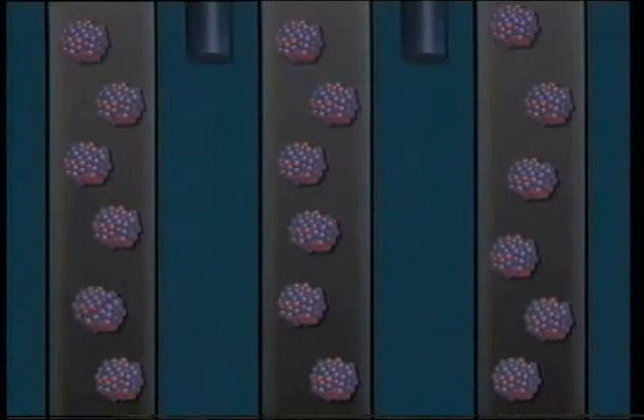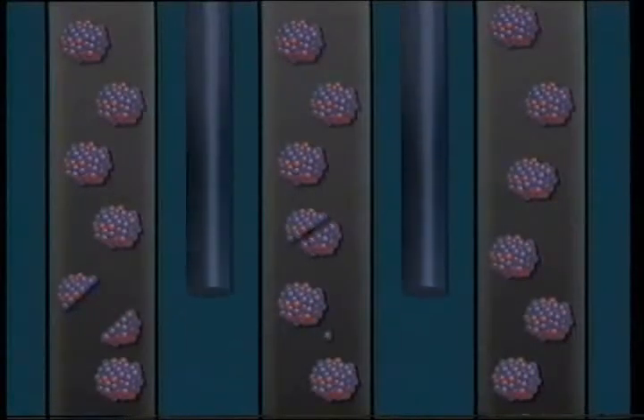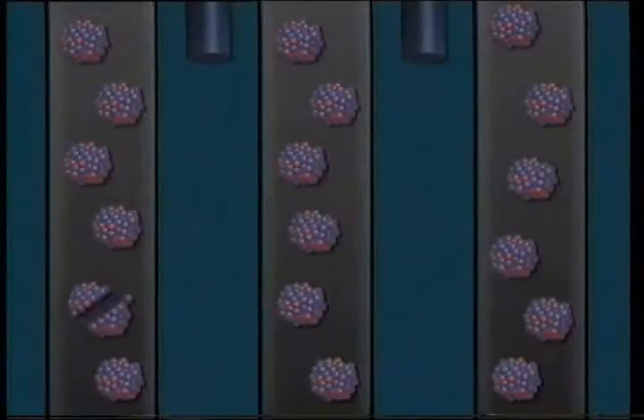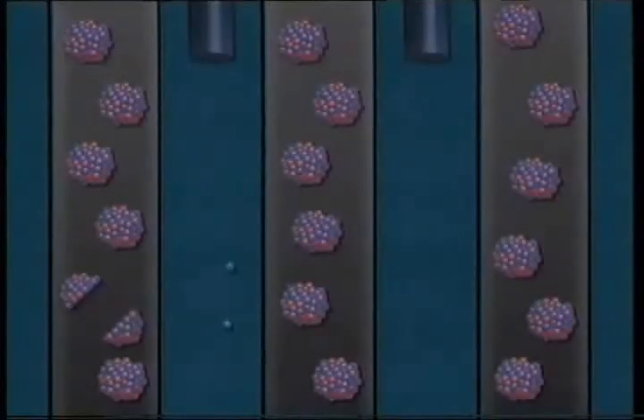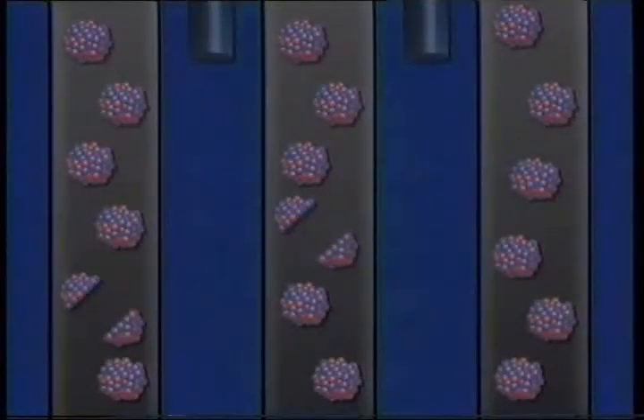Should reactor shutdown be necessary, this can be achieved either by lowering the control rods into the core or by injecting boric acid into the water coolant. So, different methods exist to perform one safety function. If a system fails, one or more alternatives are immediately and automatically available.